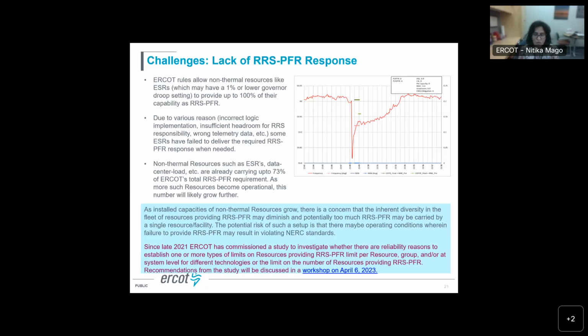Now, due to various reasons, be it incorrect logic, insufficient headroom, wrong telemetry, etc., we have seen that some energy storage resources have failed to deliver the required RRS PFR response when needed. The graphic here is showing you one example wherein you're seeing a frequency trace from a unit trip event, and the blue line represents output from a particular energy storage resource.